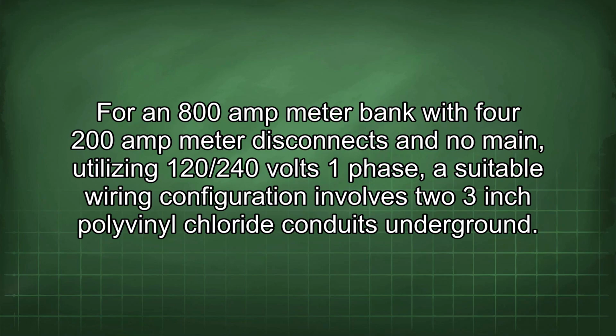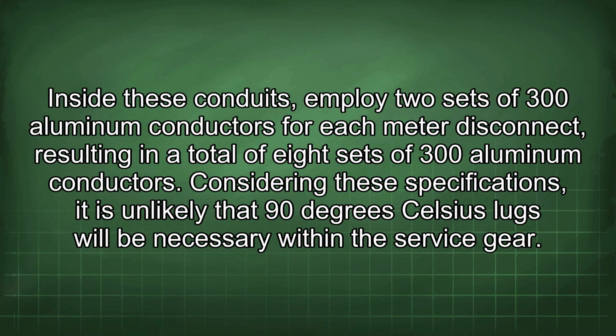For an 800 amp meter bank with 4 200 amp meter disconnects and no main, utilizing 120/240 volts single phase, a suitable wiring configuration involves two 3-inch polyvinyl chloride conduits underground. Inside these conduits, employ two sets of 300 aluminum conductors for each meter disconnect, resulting in a total of 8 sets of 300 aluminum conductors.